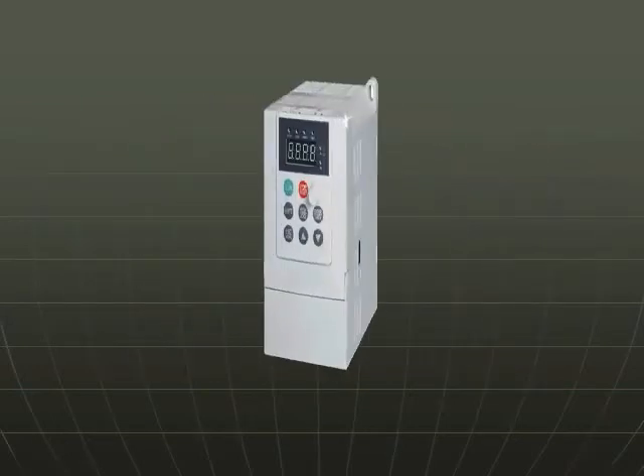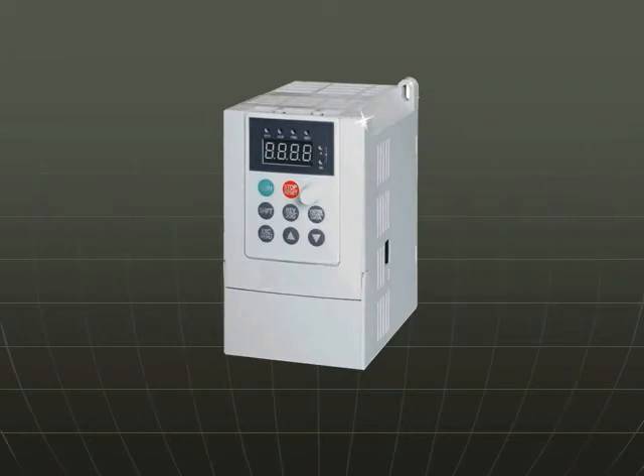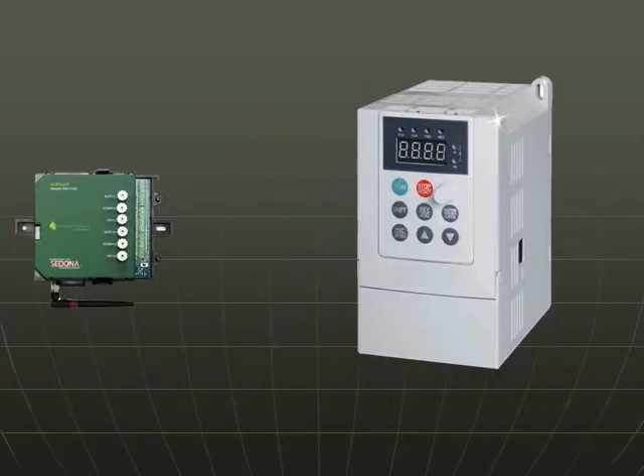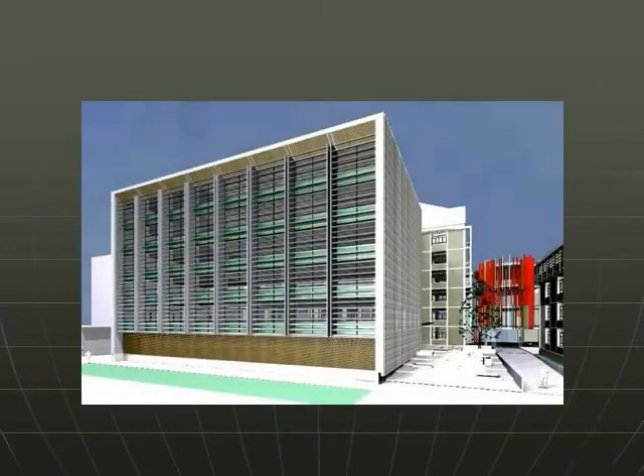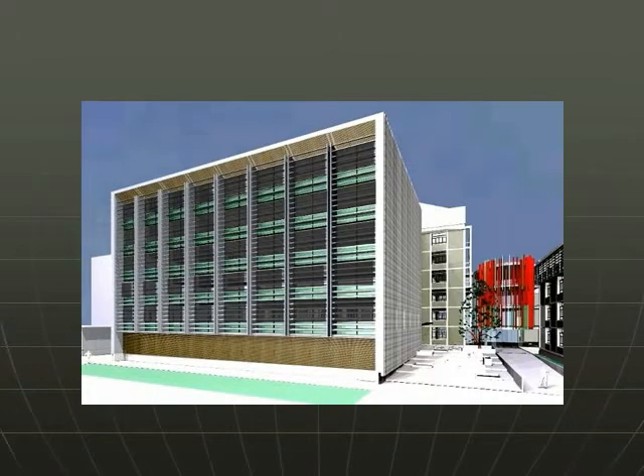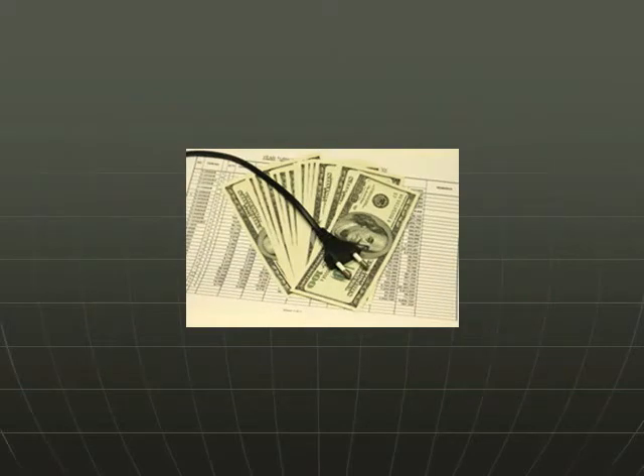Many facilities have not purchased variable frequency drives, or VFDs, for their fans and pumps yet. The ecWizard increases their ability to save energy, making the entire energy saving system, including new VFDs, that much more affordable to purchase. Large fan systems utilize a time clock where entire floors or buildings are shut down or started to accommodate various occupied or unoccupied requirements. By individually customizing time clock schedules for each room thermostat, we can save a large amount of money and energy. Buildings with varying occupancies and vacancies have an even greater opportunity for savings.